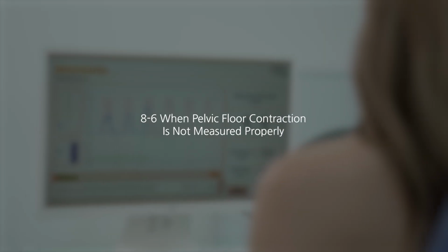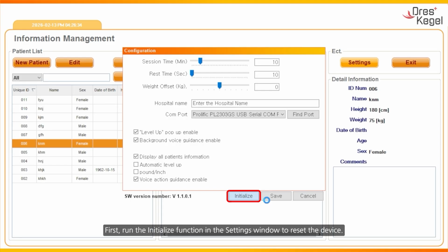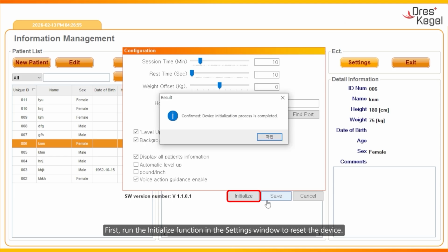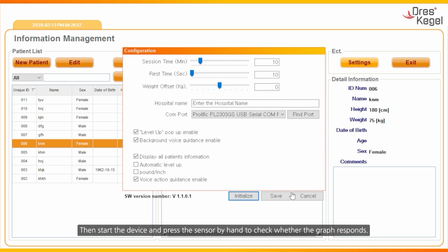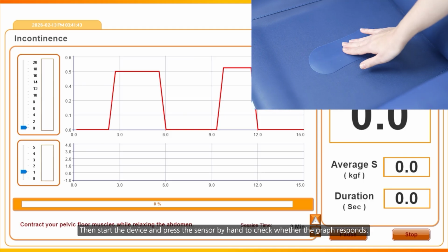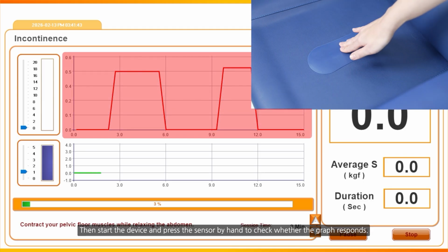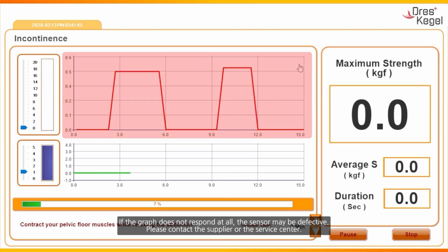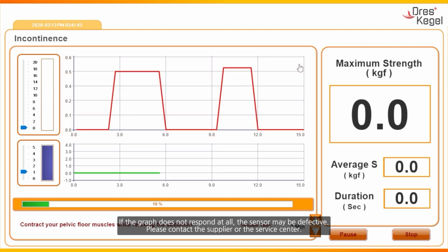Number 8-6. When pelvic floor contraction is not measured properly. First, run the initialize function in the settings window to reset the device. Then start the device and press the sensor by hand to check whether the graph responds. If the graph does not respond at all, the sensor may be defective. Please contact the supplier or the service center.